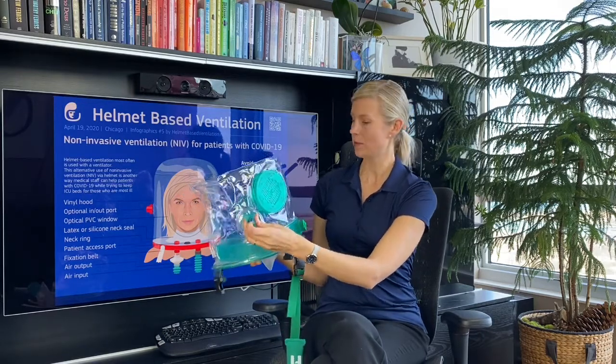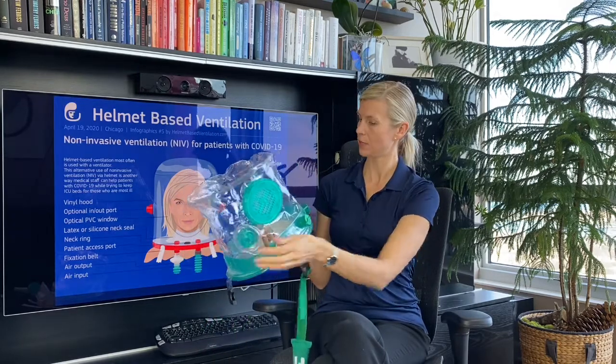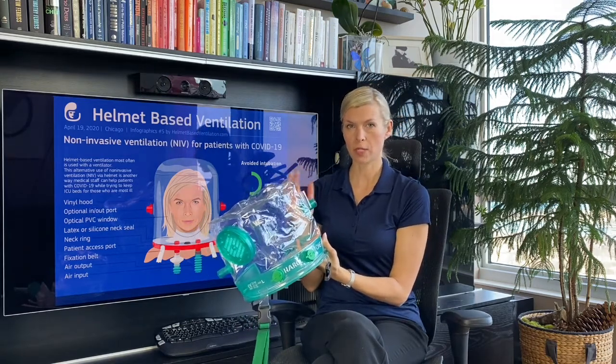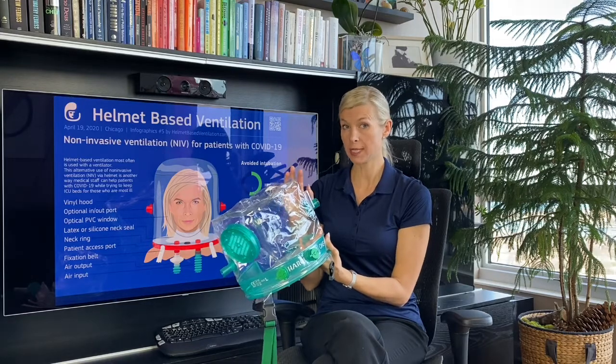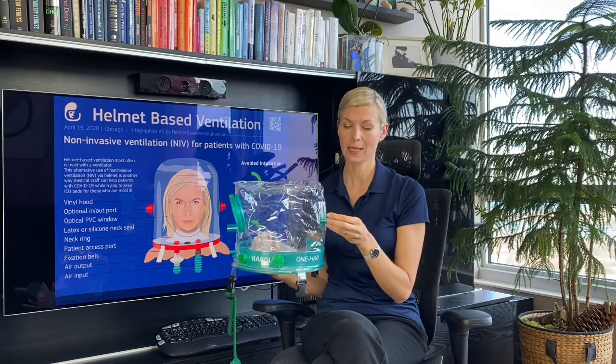The inlet and outlet ports are on the hood part, and what is nice is that on the outlet side you have a built-in manometer. The manometer is very important to measure actual pressures inside the helmet, especially during helmet CPAP therapy. Studies showed that the pressure can actually be higher in a helmet than what is set on a PEEP valve, especially spring-loaded PEEP valves. By having this manometer on the helmet you can prevent too-high pressures and provide adequate ventilation for the patient.